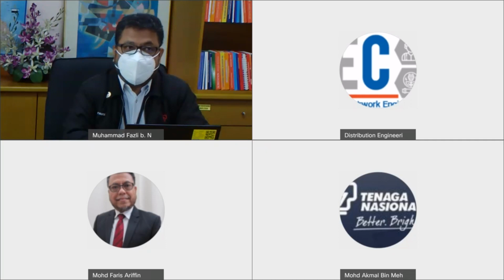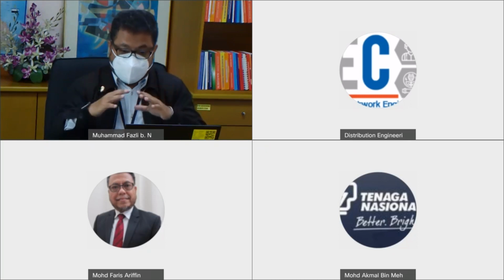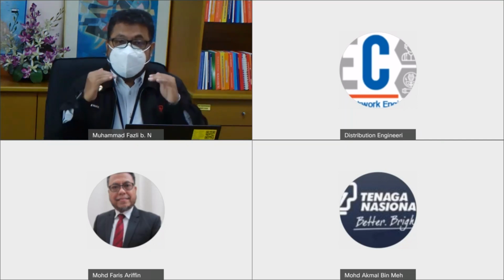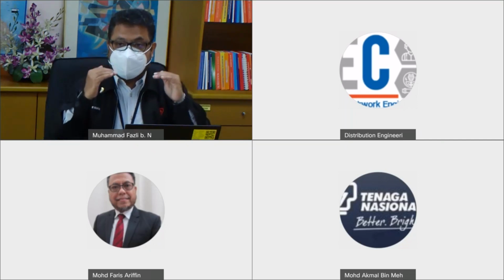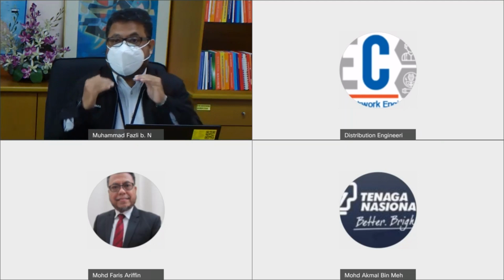For the mesh system, you have to look at the performance of the earthing for lightning using the frequency domain. I've shown you earlier that the performance in the frequency domain is very important to analyze the grounding of the system. For example, if you have a power frequency failure or interruption at 50 hertz, the ground potential rise on a mesh system will rise uniformly. That is very important to avoid step voltage.